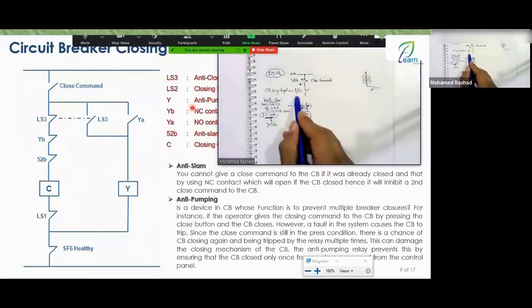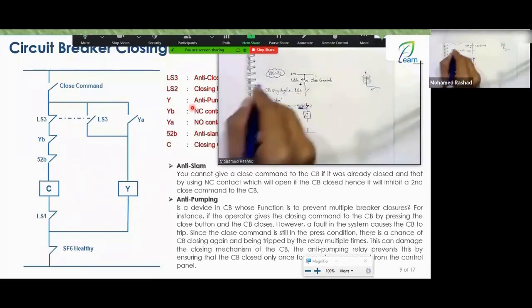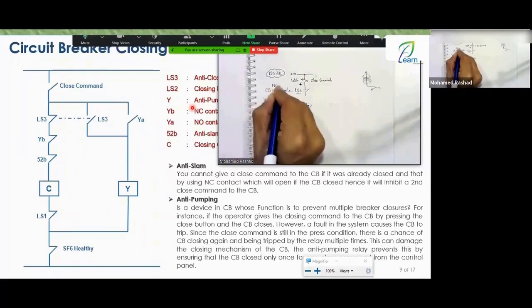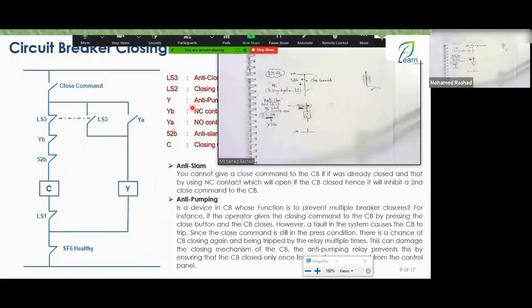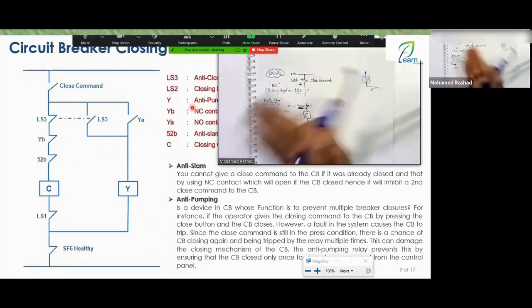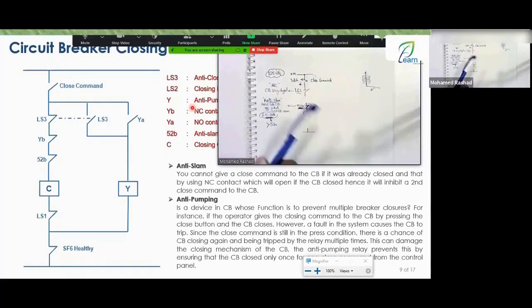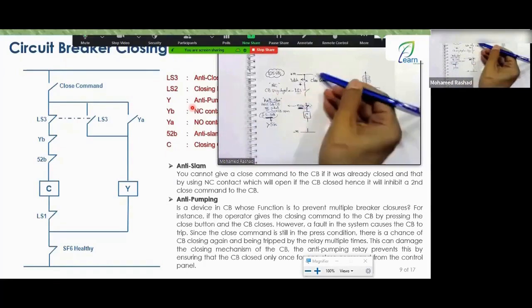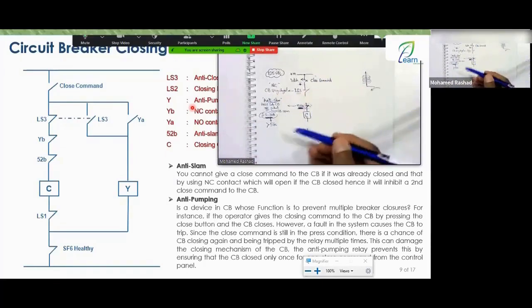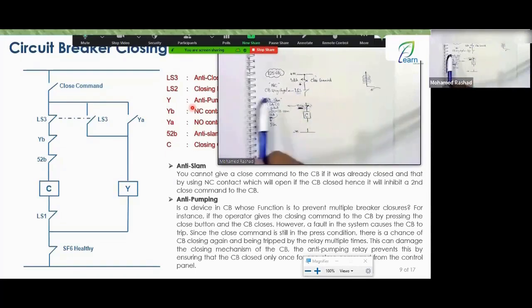Okay, and you have this normally closed contact. It's closed when the spring is charged. So as long as the spring is charged, it keeps passing the close command. If the spring is not charged, this contact opens. So it keeps giving a close command, but the breaker mechanically won't close at all. So there's no need to connect the close command to the closing coil, because it might burn out since it won't close mechanically anyway, right? Am I wrong? Right.